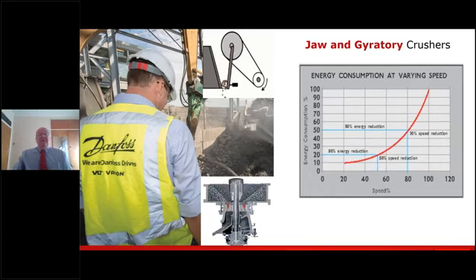If you lift your foot, obviously the speed of the vehicle will start to slow down. You'll still reach your destination, be it a little bit later. However, you'll reduce your fuel consumption, so you'll be saving money. And it's basically the same with a variable speed drive, and I'll go through the graph just now. So electrical variable speed drives are the most efficient control method. Why? Because they save energy, they decrease the CO2 emissions, which is a factor that all industry is looking to achieve, and it minimizes the total operating costs. Now, by utilizing a variable speed drive, it actually replaces the mechanical control devices, such as valves, fan inlet vanes, hydraulic couplings, and dampers, which are quite often used in the different mining processes.